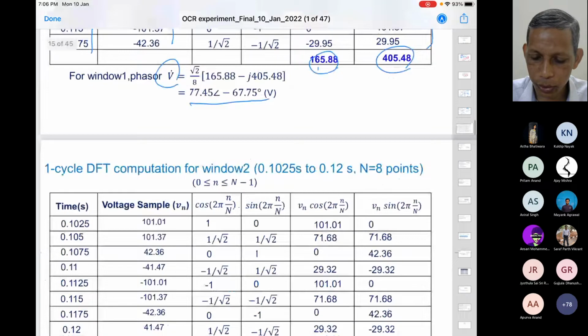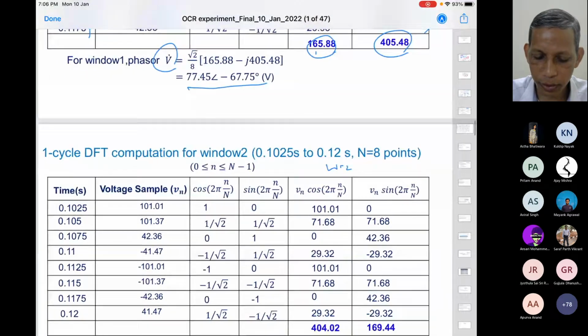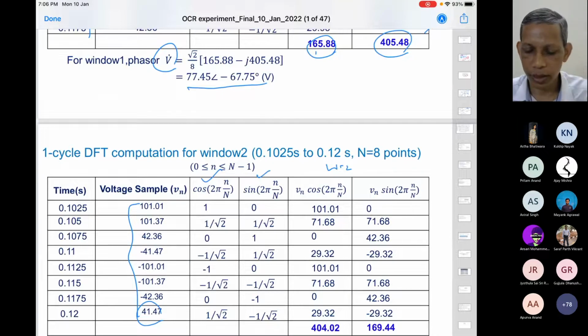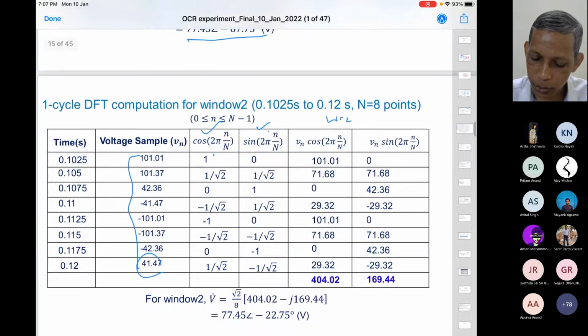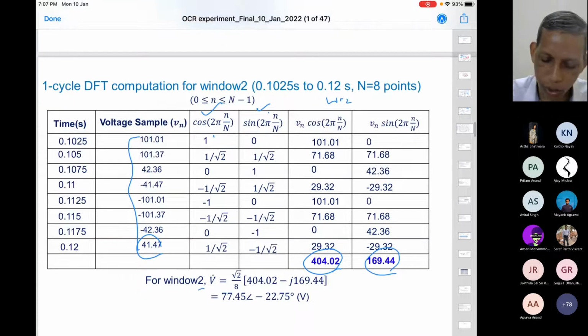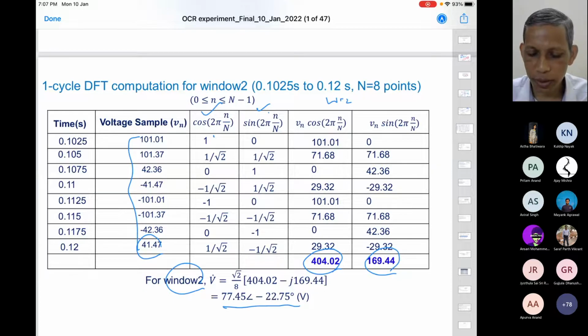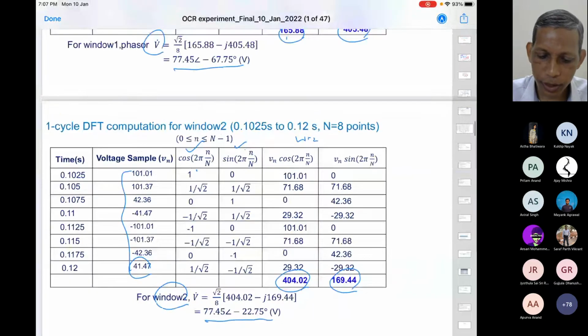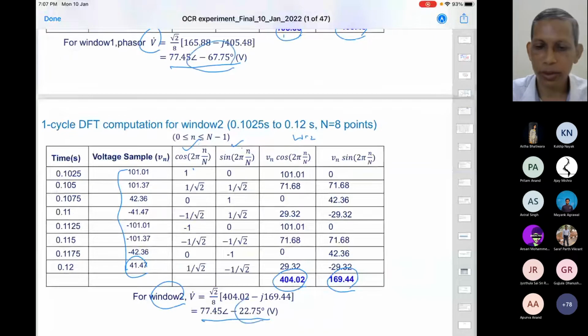Now when we go to window 2, the sample is shifted. Older sample is discarded, new sample is being acquired. So these are the new samples. Same for your coefficients, the same 8 weights are there, 8 here and 8 here. You multiply these samples like that, then I get the corresponding summation of the real part and the imaginary part to be like this. And when I apply this in window 2, I get 77.45 with minus 22.75. Only that changes: this is 67 and this is 22. A shift of plus 45 degrees happens to be there.